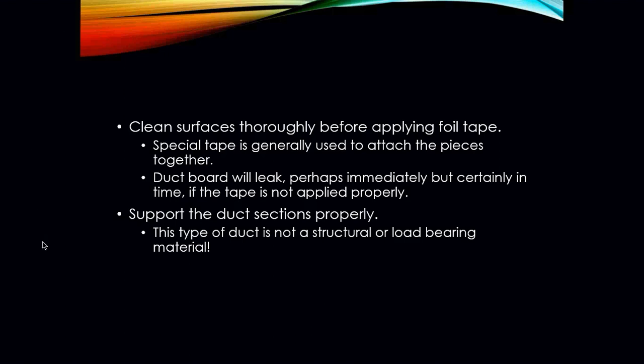Clean surfaces thoroughly before applying any sort of foil tape when you are dealing with fiberboard. You have to use special tape, which is generally used to attach the pieces together. Okay, we call that aluminum tape. Your ductboard will leak, perhaps immediately, but certainly with time, especially if that tape is not properly applied and/or that ductboard is not properly cleaned before you put the tape on.